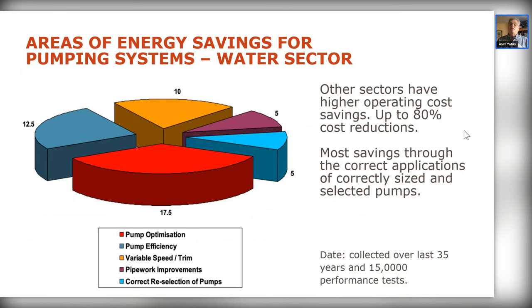On optimization, general savings are in the region of 17.5 to 20% — more with variable speed, slightly less with fixed speed. On pump condition: from around 2,500 to 3,000 pumps personally tested and over 15,000 tests reviewed, the average shortfall in pump performance is 12 to 14% — 12% for water applications, 14 to 15% for wastewater.